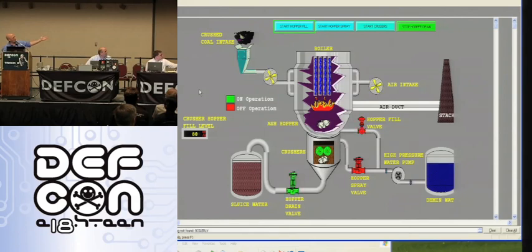You saw what's supposed to happen. The drain valve opened for a second and closed again. The fill valve open, and you're just filling that hopper all the way up. Eventually what's going to happen is water is going to get inside the boiler. You could put out the flame, possibly cause a boiler explosion, at least hypothetically.